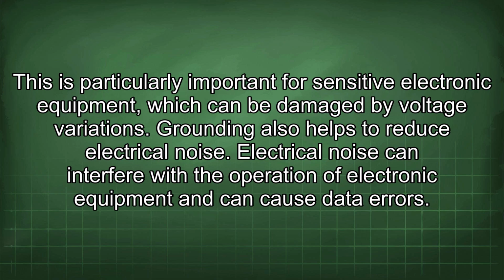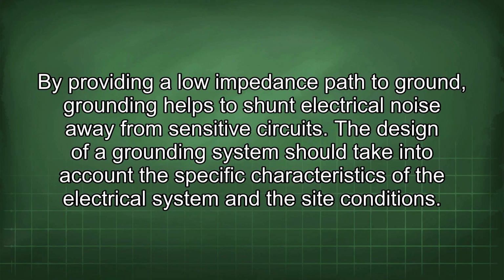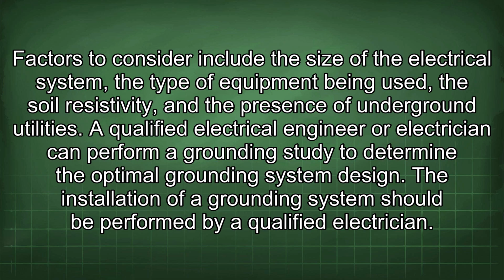Grounding also helps to reduce electrical noise. Electrical noise can interfere with the operation of electronic equipment and can cause data errors. By providing a lower impedance path to ground, grounding helps to shunt electrical noise away from sensitive circuits. The design of a grounding system should take into account the specific characteristics of the electrical system and the site conditions. Factors to consider include the size of the electrical system, the type of equipment being used, the soil resistivity, and the presence of underground utilities. A qualified electrical engineer or electrician can perform a grounding study to determine the optimal grounding system design.